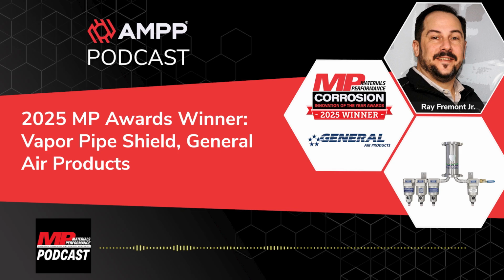Vapor Pipe Shield is fully mechanical with no electrical connections. It's simply piped directly in line between the air compressor and a dry pipe valve. It's easy to install as an air maintenance device, easily maintained, and makes corrosion mitigation in any dry or pre-action fire sprinkler system simple, efficient, and highly cost-effective.